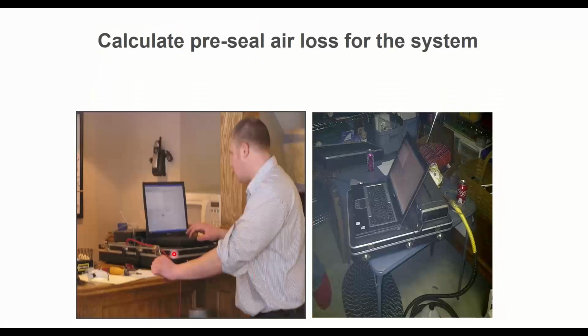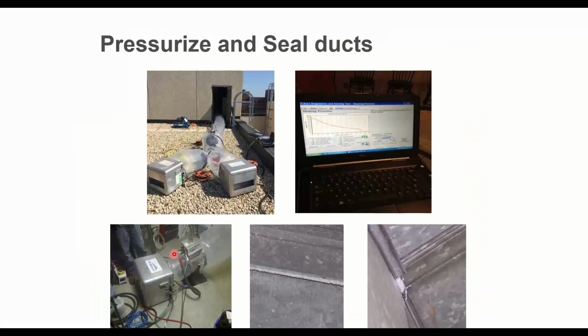This whole process is driven off of a laptop or a tablet. This is an older computer picture, but same idea. So that equipment, the manometer inside there, the fan system, and the glue injection system are all hooked up to a microprocessor, and that is controlled directly from a laptop. When we start doing larger commercial applications, sometimes we will have to use two fan boxes, like they were using on this particular project. I believe this was an Airway Systems job too. But one fan wasn't big enough because the duct system was pretty large. So in order to generate enough pressure, they twinned two fan boxes together. So they got more airflow moving through here.